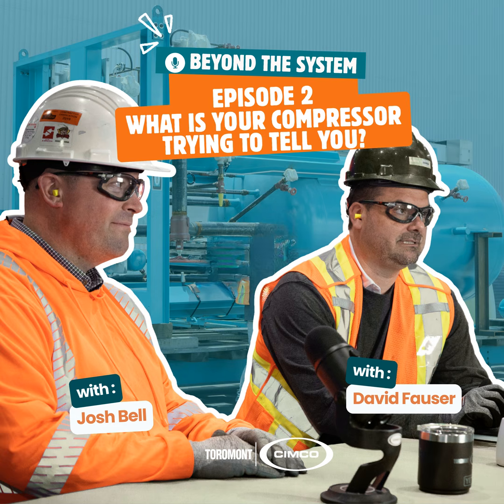On a reciprocating and screw compressor, there is a tolerance for leakage. Just because there's some leaking doesn't mean that it's a problem. But if it's leaking out of the shaft and not through the drip tube into the collection bottle, that's a problem that needs to be addressed. So when I'm doing inspections, I always want to check the shaft seal, see if it's coming out the shaft. I want to check the oil bottle to see how much it's filling up. And then in the logbook under your inspection section, note how much that bottle is filling up, because eventually you're going to walk in and it'll be overflowing. And is it overflowing in one day, or is it overflowing in 6 months?